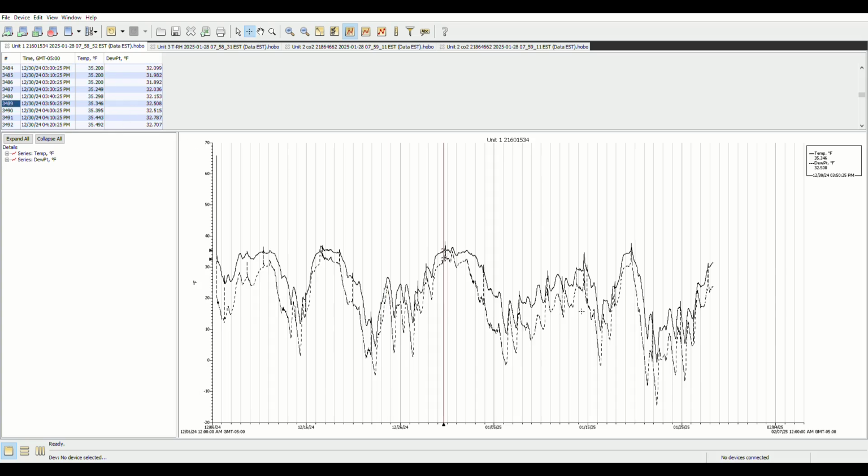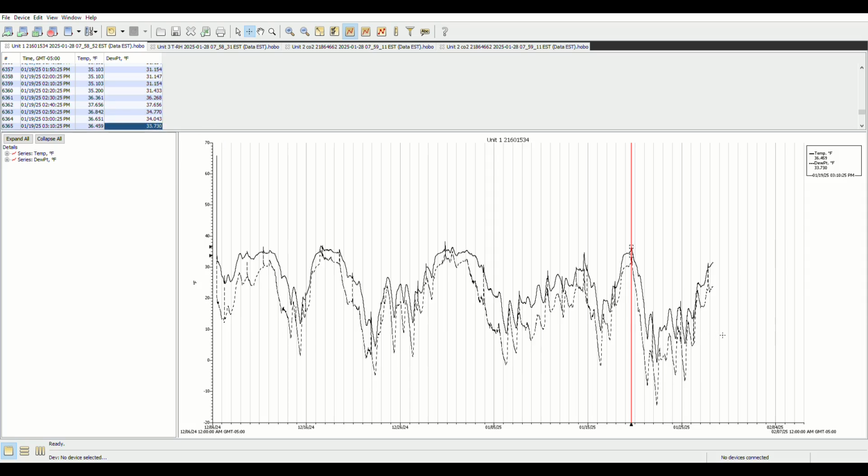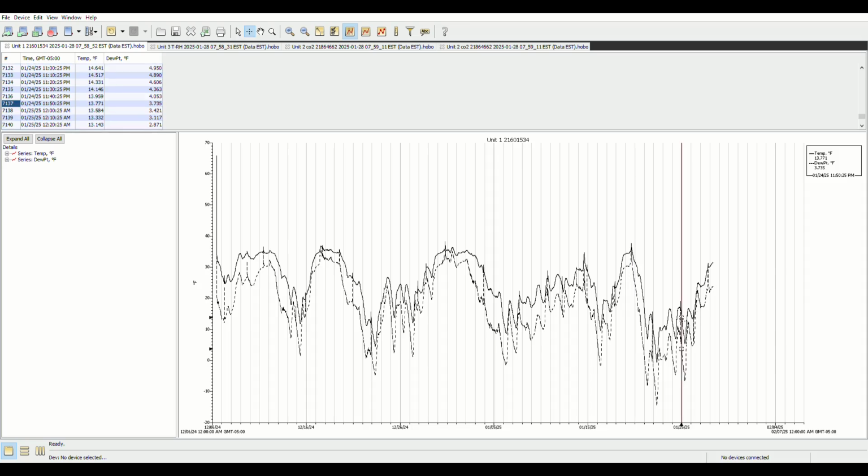And I went through all of these, anything that got close, and see like a 37 degree dew point here. It's 37 degrees inside the cavity, but then dissipated quickly. So it looks like the concern has been alleviated with the remedies that have taken place. And then we'll look at unit 3.